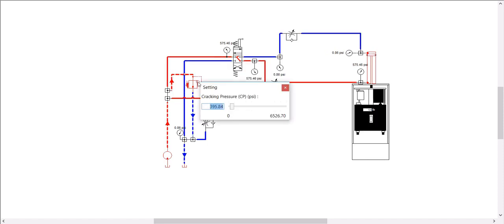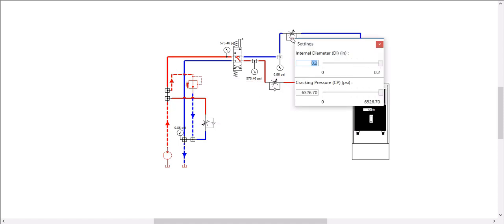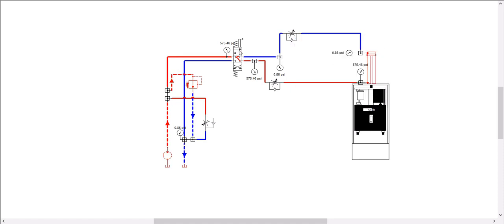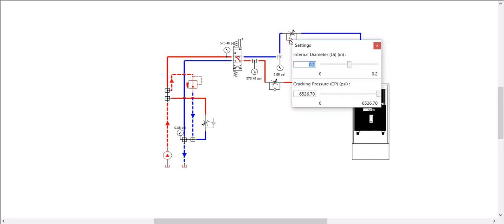We'll use the pressure relief valve to set the system pressure, which is displayed in the pressure port of the directional valve. We'll use around 600 psi. By metering the flow of oil into the cylinder, we will be able to adjust the speed of extension and retraction.